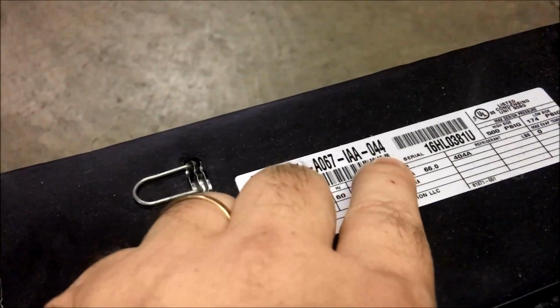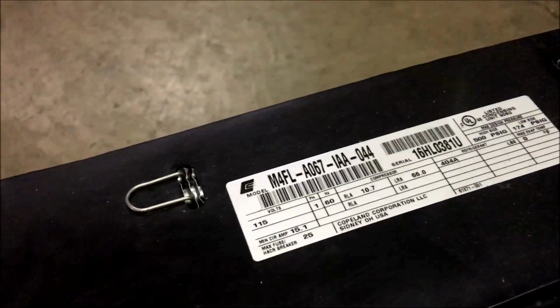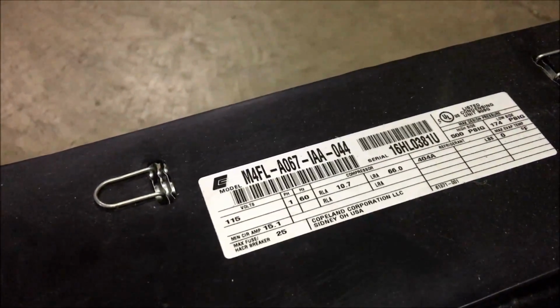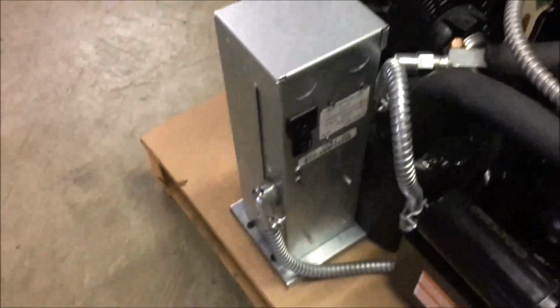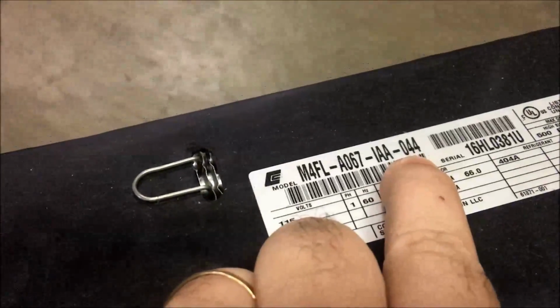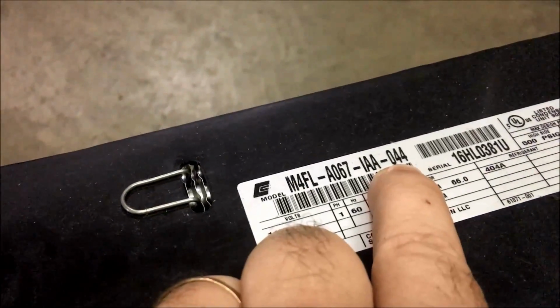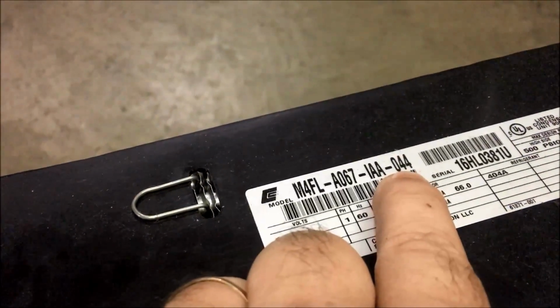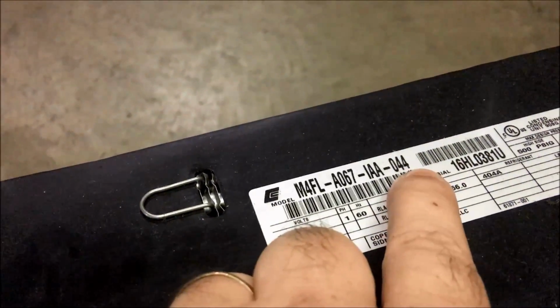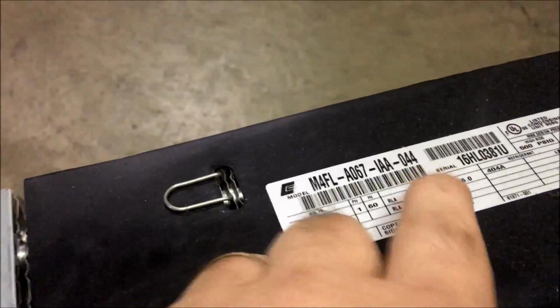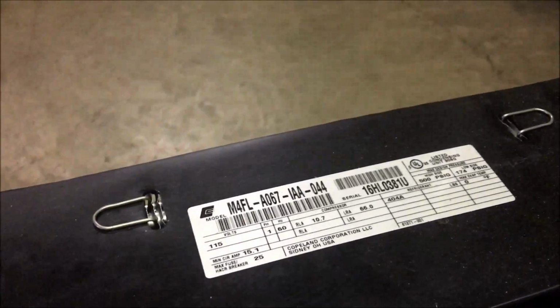In this case, 4 means this is an OEM special unit. So this unit right here was designed specifically for a certain OEM in order to fit into their cabinet, with special connections. You see here, this one has a special electrical box on it, and it also has some refrigerant connections on it to make it easier to connect into the system. So anytime you see a 4 or a 6 in this middle digit, that means that it's going to be a customer or an OEM special unit. And then the last digit doesn't have any real significant meaning. It's just another variation of the unit.